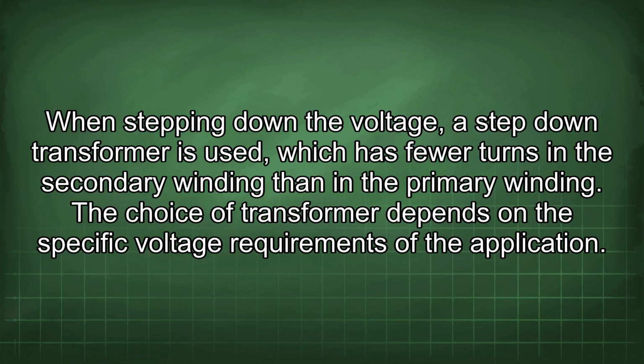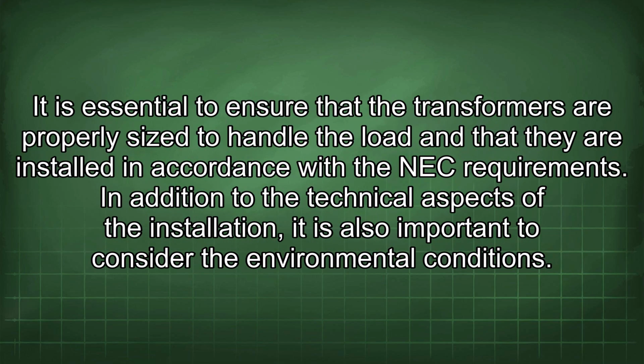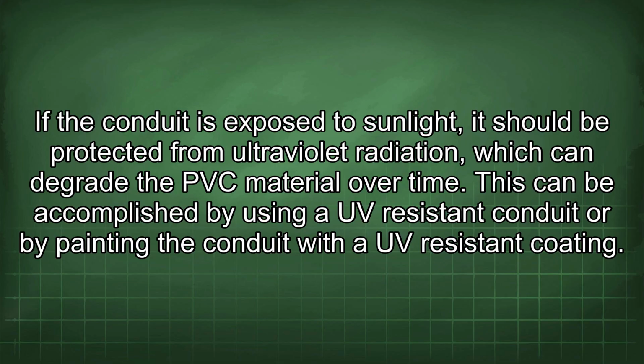The choice of transformer depends on the specific voltage requirements of the application. It is essential to ensure that the transformers are properly sized to handle the load and that they are installed in accordance with the NEC requirements. In addition to the technical aspects of the installation, it is also important to consider the environmental conditions. If the conduit is exposed to sunlight, it should be protected from ultraviolet radiation, which can degrade the PVC material over time. This can be accomplished by using a UV-resistant conduit or by painting the conduit with a UV-resistant coating.